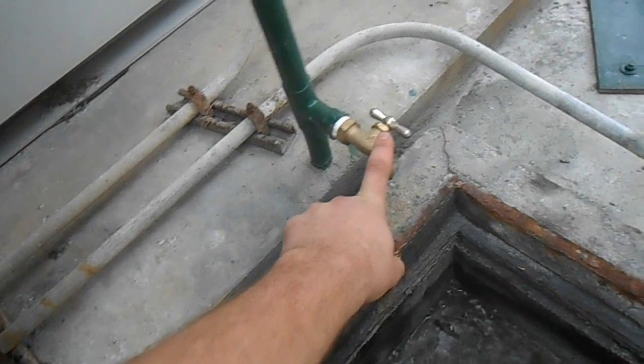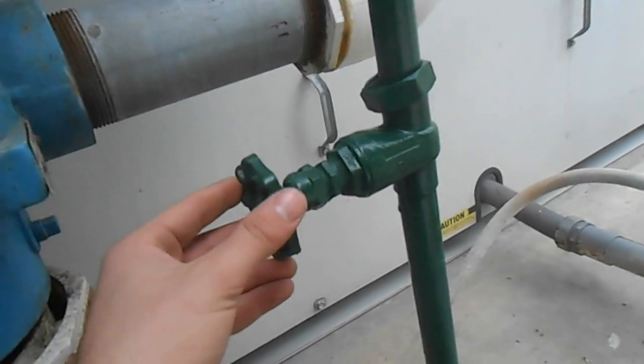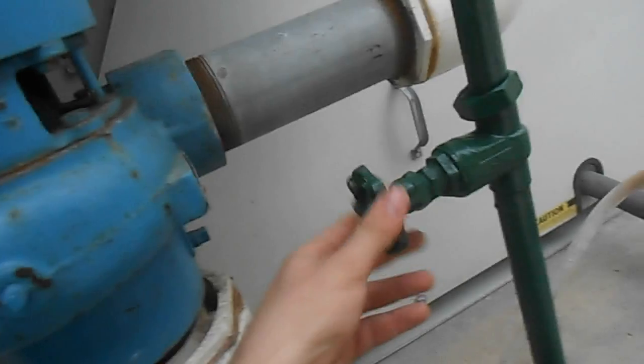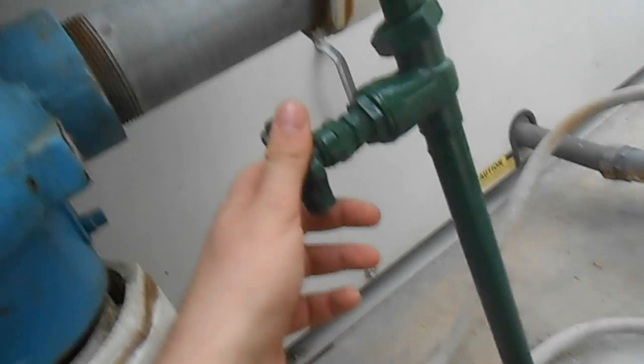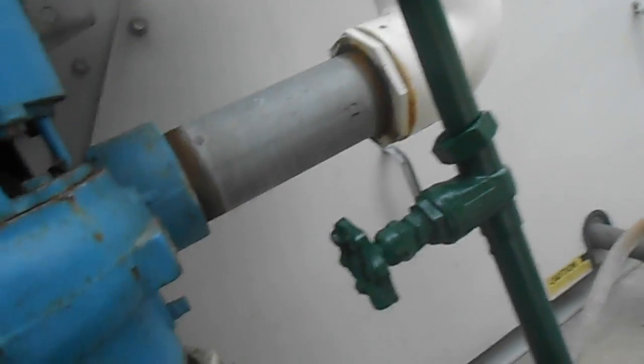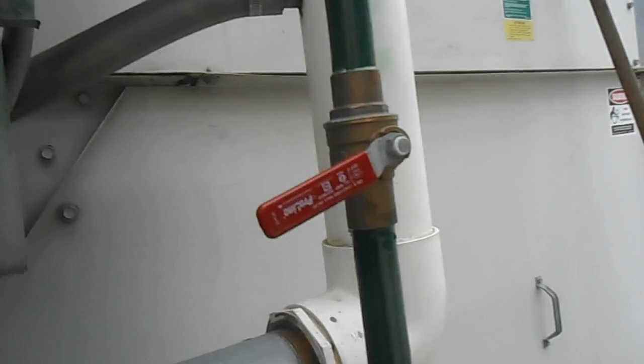It pops up over here. Now, we replaced this hose bib that was leaking, so we did that. And here was the old shutoff for our water solenoid valve up there, but it didn't shut off. As you may know, old gate valves often, especially if they haven't been exercised, won't shut off. That was the case with this one. So that's why they did a new ball valve up here.